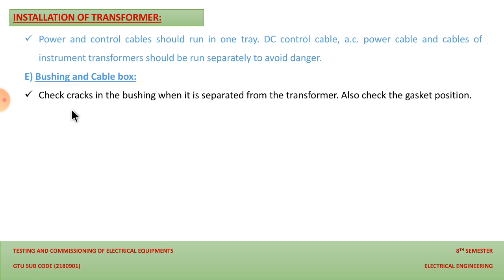The paper insulated cable has to be connected generally. Then the cable ends should be sealed to prevent absorption of moisture. This is the most important point. If the cable absorbs moisture, the insulating property of the cable will deteriorate. Also, erosion of the cable will take place at the joint, at the place where we are joining the cable. The boxes should be filled with oil or compounds after making the connection. So this is necessary. It is filled with oil so that it will not absorb any moisture.